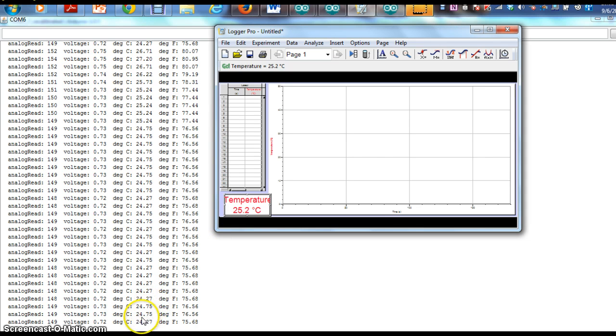The temperature on the sensor is bouncing between 24.75 and 24.27. So it's not perfect, but it is getting at least about a degree closer pretty consistently, sometimes even closer than that. At any rate, the whole idea about calibrating is that you are trying to make sure that your data is as accurate as possible. And that means making sure that the instruments you measure with are as accurate as possible.